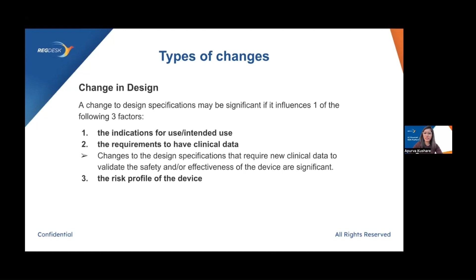A few examples of that would be introducing a new hazard or hazardous situation, or, when it comes to design changes, a change to the severity or the likelihood of the harm occurring, and also introducing any new required risk mitigation actions. On the other hand, to give an example of a non-significant change, the risk assessment conclusions are basically not altering the device or the design change, and the device performs the same as the original design submitted in the previous application. So you're basically using the same parameters to assess the risk. In this situation, it's likely considered to be non-significant.